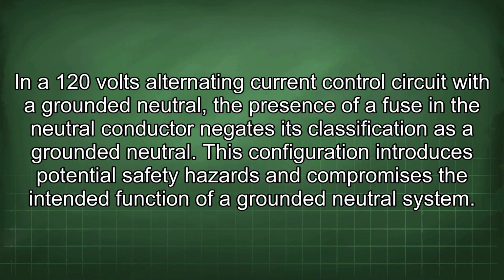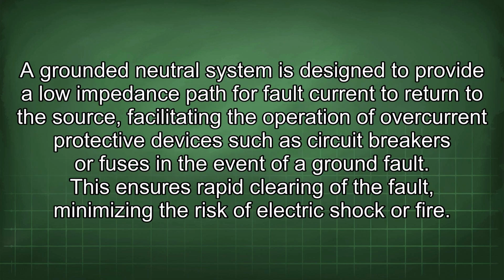In a 120 volts alternating current control circuit with a grounded neutral, the presence of a fuse in the neutral conductor negates its classification as a grounded neutral. This configuration introduces potential safety hazards and compromises the intended function of a grounded neutral system. A grounded neutral system is designed to provide a low impedance path for fault current to return to the source, facilitating the operation of overcurrent protective devices such as circuit breakers or fuses in the event of a ground fault. This ensures rapid clearing of the fault, minimizing the risk of electric shock or fire.